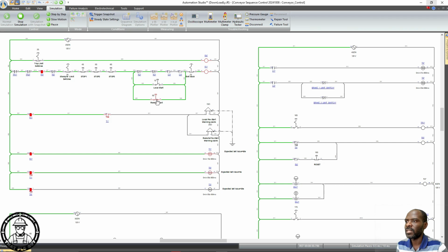Okay, so the preset alarms are off, T5 picks up, and then of course C1 is energized. Thereafter we're waiting on T3 and T4. Okay, so T4 is actuated. So T4 comes on way before T3. Okay, so you notice that T4 is energized before T3.